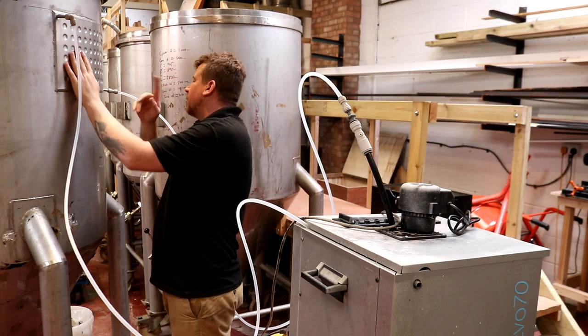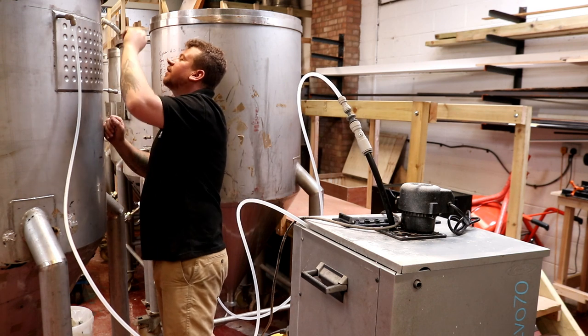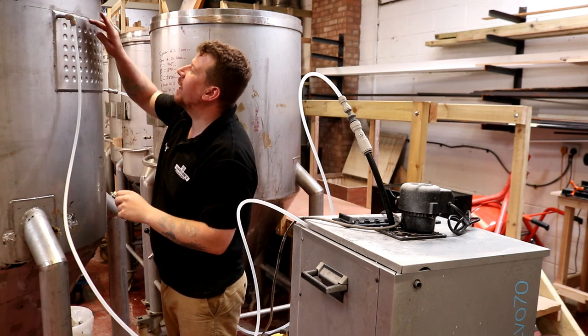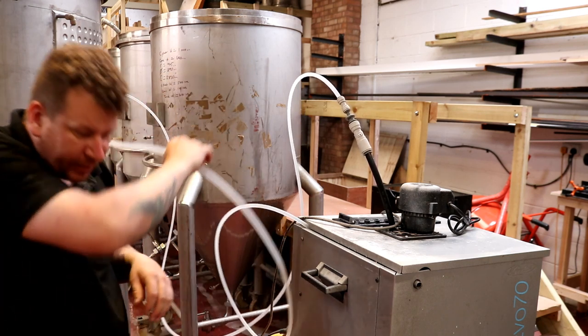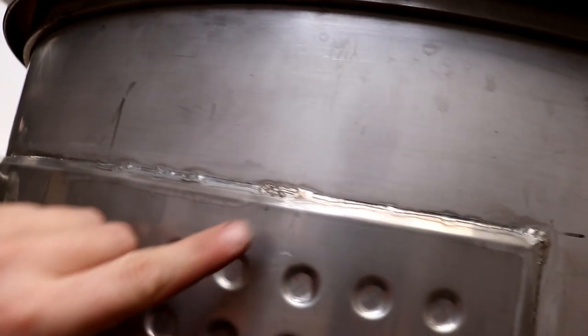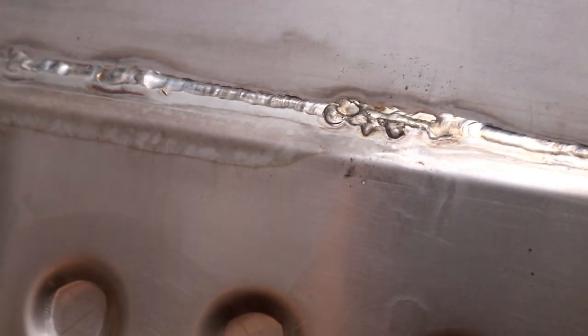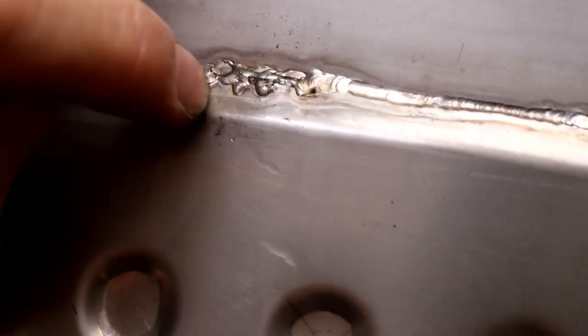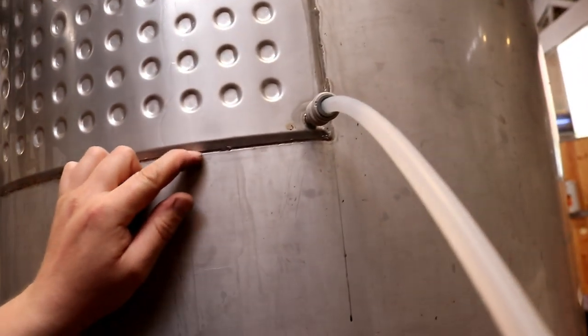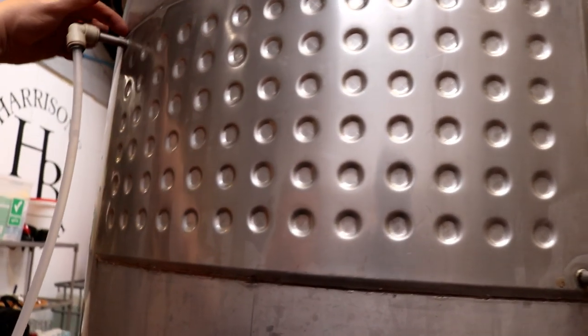Right, there we go and that's why we're doing this. So I have found a leak. There we are. So I'll go and get a pencil and we'll draw around that because obviously the pen isn't going to be much good. So there you can see, just that little spot there, it's just weeping out look. So they would have had glycol weeping out there all the time. So because this plate is actually at the top of the tank and it really wants to be down the bottom, what I'll probably do is chop this whole thing off just around the edge with the slitting disc and move it down to here so it's the same as the other ones.